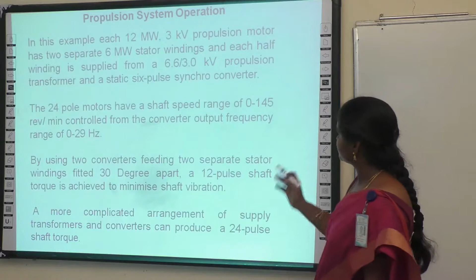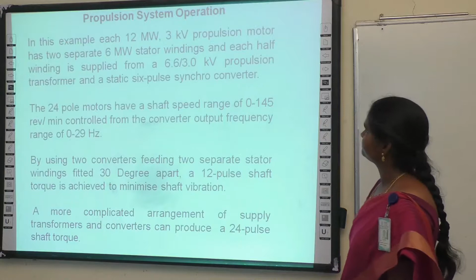The 24-pole motors have a shaft speed range of 0 to 145 revolutions per minute, controlled from the converter output frequency range of 0 to 29 Hz. By using two converters feeding two separate stator windings fitted 30 degrees apart, a 12-pulse shaft torque is achieved to minimize the shaft vibration. A more complicated arrangement of supply transformers and converters can produce a 24-pulse shaft torque.